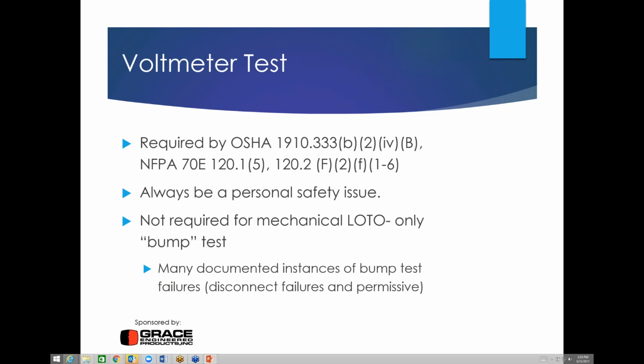Again, going back, John had mentioned it's not required to use a voltmeter for mechanical lockout only, when you're going to be working on non-electrical equipment. But it's kind of an interesting change at this point. A lot of applications today don't have the traditional start button on the equipment. They have a start button on the PLC, which makes it a little bit difficult to hit the try button. But you still need to do your bump test or your try test.